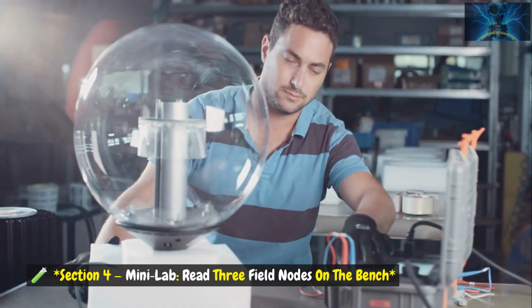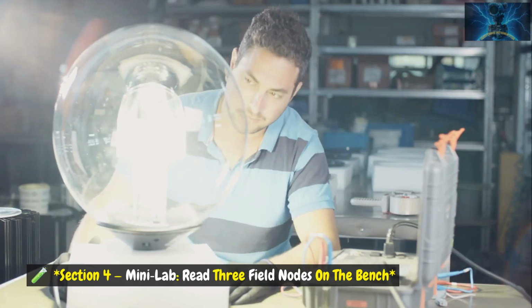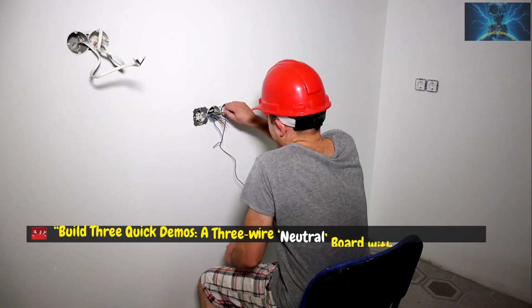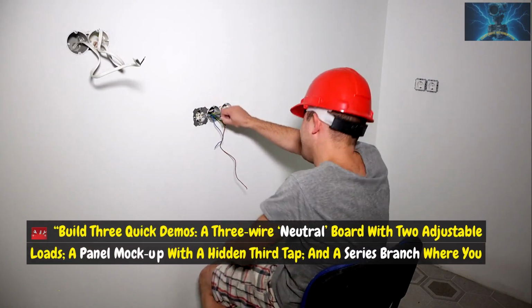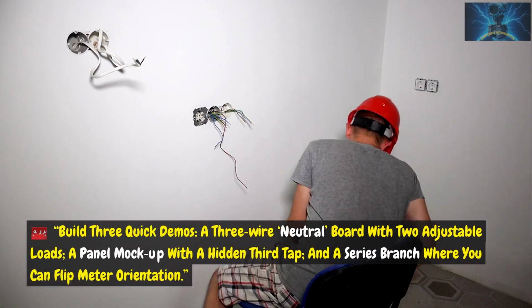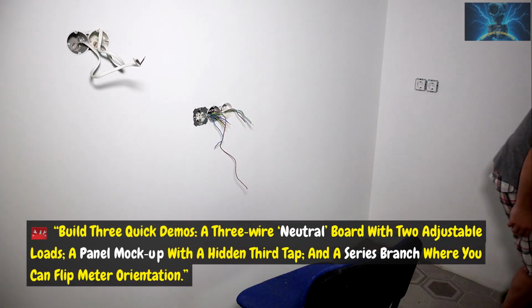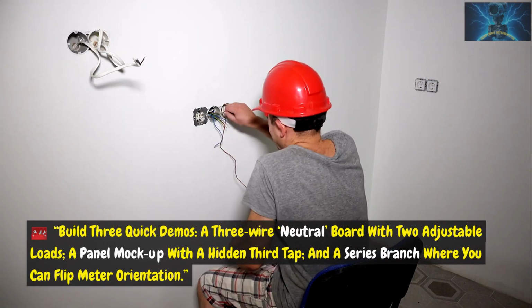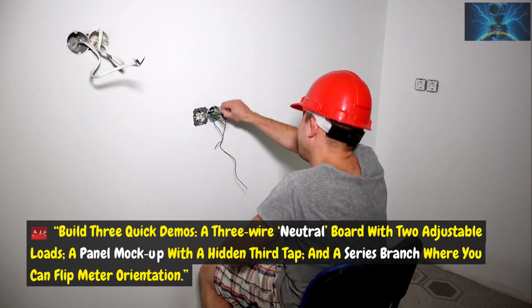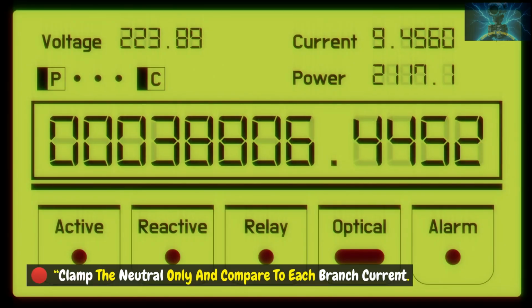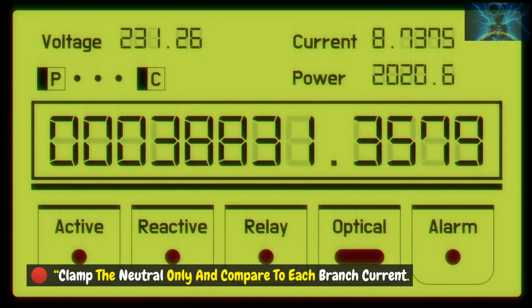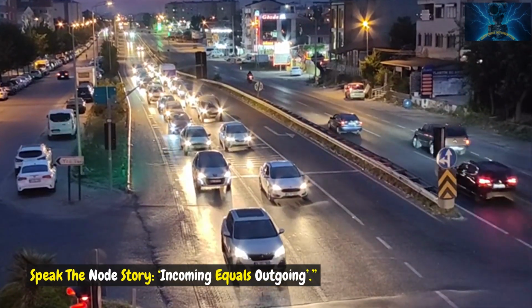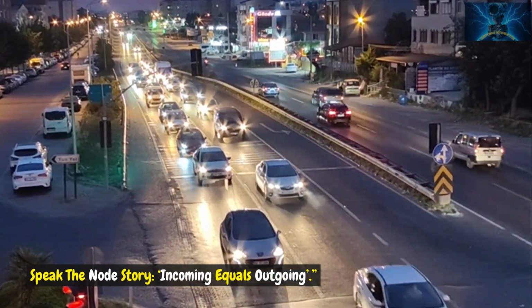Section 4. Mini-lab. Read 3 field nodes on the bench. Build 3 quick demos: a 3-wire neutral board with 2 adjustable loads, a panel mock-up with a hidden 3rd tap, and a series branch where you can flip meter orientation. Clamp the neutral only and compare to each branch current. Speak the node story. Incoming equals outgoing.